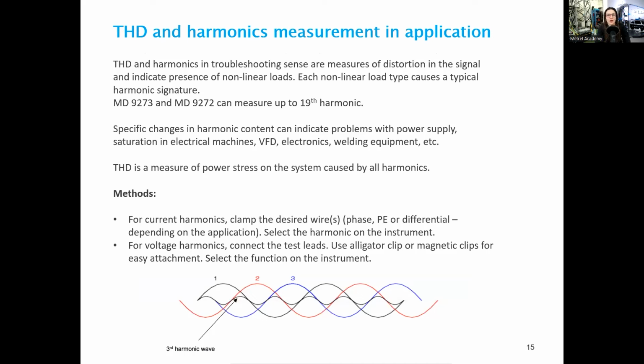We have the THD and harmonics measurements available in this clamp. So we're going to first look at a little bit of theory behind them, and then we're going to go ahead with the applications for troubleshooting. The harmonics are a mathematical way of describing signal shapes as a sum of signals at different frequencies. The frequencies that are summed in harmonics are the base frequency and its integer multiples. So, for example, in an installation, we have the base frequency of 50 Hertz or 60 Hertz. The second harmonic is going to be at 100 or 120 Hertz, the third at 150 or 180, and so on.